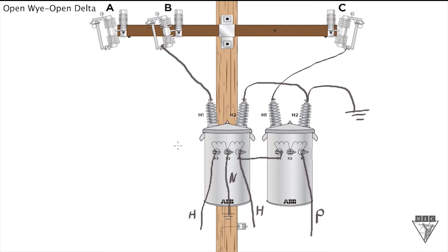One thing with an open bank, it's 57.7 percent as efficient as a closed bank where you have three transformers. But it is very useful when you have a load where it's predominantly a single phase load but you also need a three phase load.